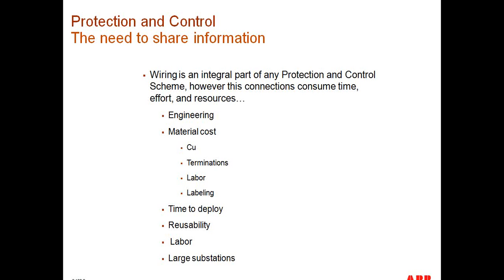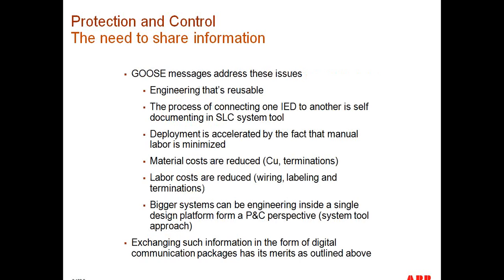And then you have the challenge of large substations, where in the case of breaker fail, there may be several connections from one device that's initiating breaker fail to the devices on the breakers that need to clear for that condition, and then all of the complexities and all of the testing that's associated with that. So, with the need to share information, how do GOOSE messages address some of these issues?